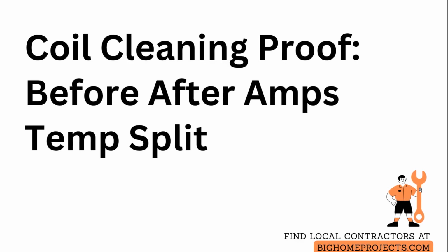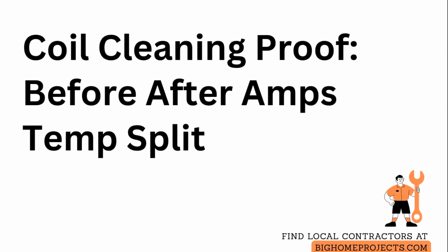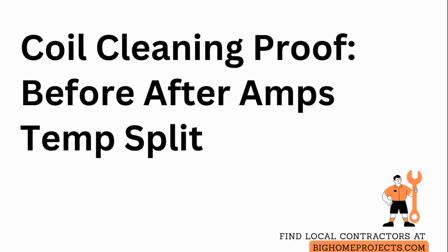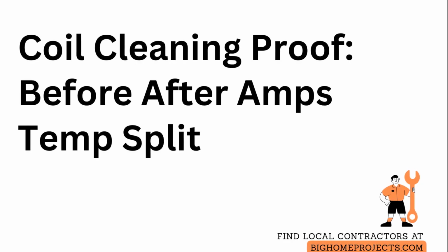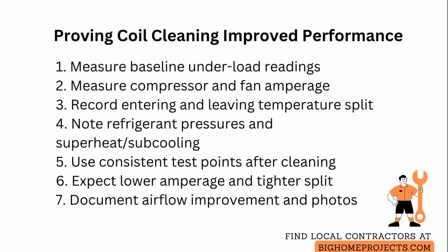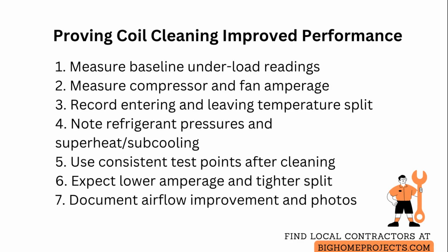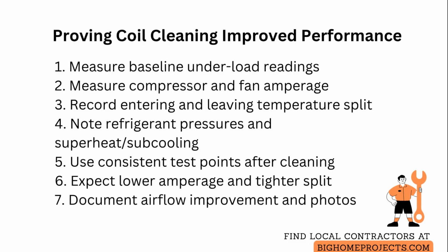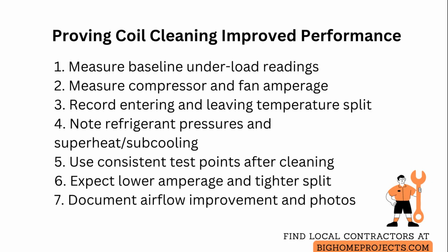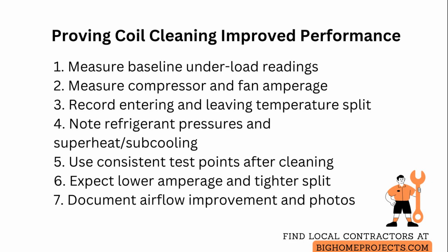A dirty coil can be the hidden cause when a system underperforms, and you can prove it by showing measurable improvements after cleaning. Start by measuring the system under load before any cleaning so you have a clear baseline. Measure the compressor and fan motor amperage with a clamp meter while the system runs at normal conditions. A dirty coil often forces higher amperage on the compressor or fan because the system works harder to move heat.